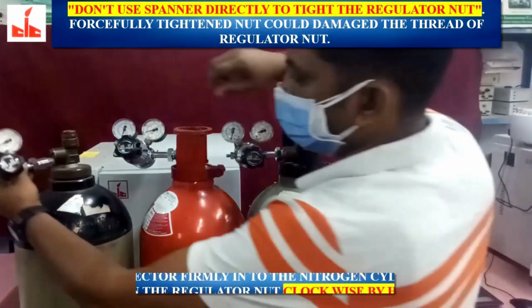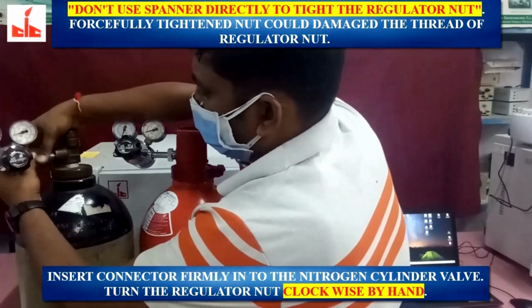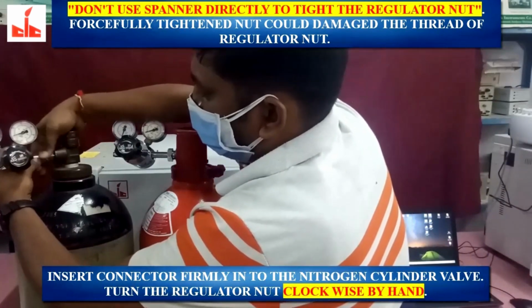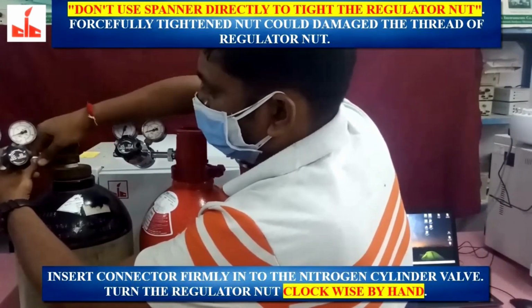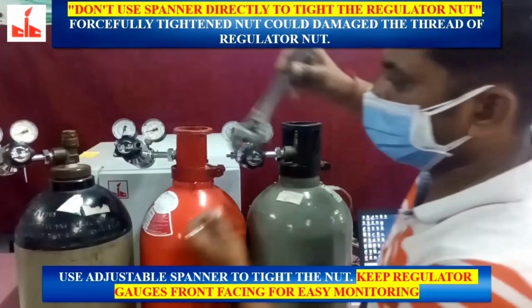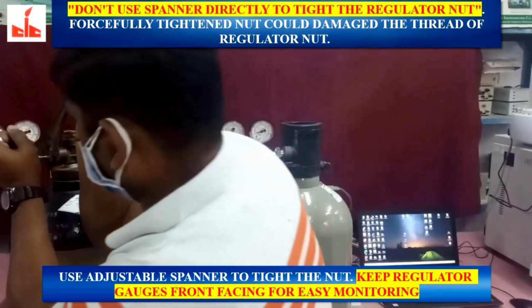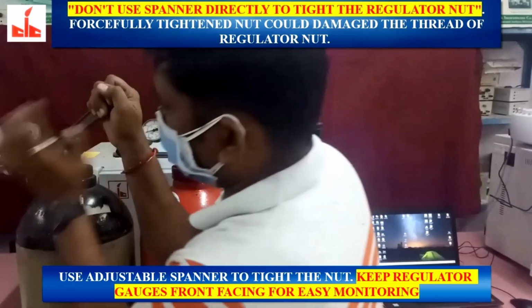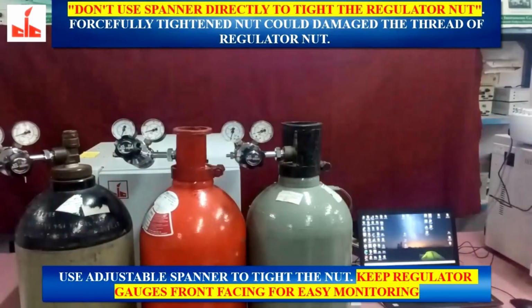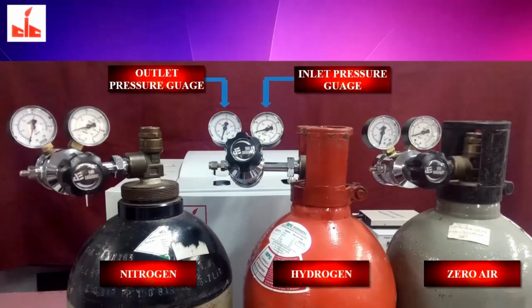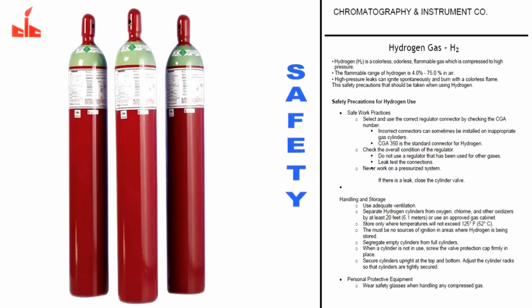Insert the connector firmly into the nitrogen cylinder valve. Turn the regulator nut clockwise by hand. Use an adjustable spanner to tighten the nut. Keep regulator gauges front facing. All the 3 regulators are mounted properly. Read this safety note when working with the hydrogen cylinders.